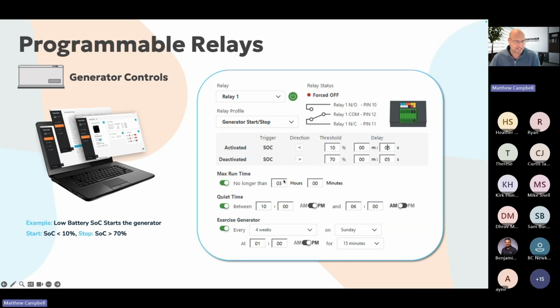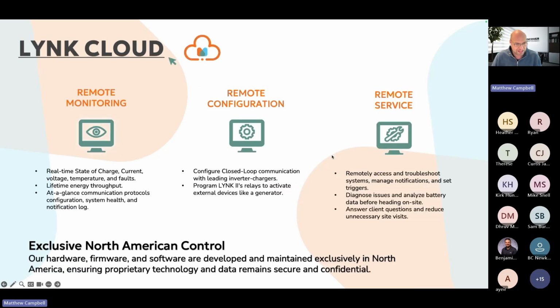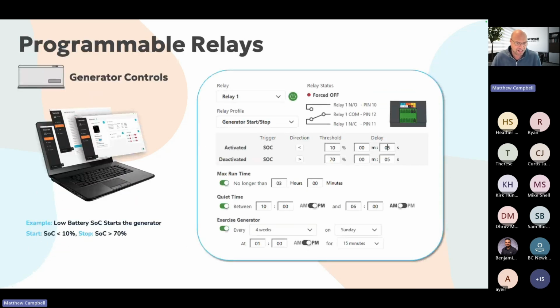Where I find this maximum runtime becomes a really powerful tool, utilizing the Lynk as opposed to using an inverter AGS, is, as a for instance, you've got your PV array set up, and you're consistently running down to an SOC of 10% at say 5 in the morning. Sorry, I'm bouncing on slides here. Sun comes up at 8 in the morning. You of course don't want to run your generator to 70%, because then you're not utilizing your PV. So you want it to run for 3 hours. Sun comes up at 8 o'clock in the morning, the generator shuts off and your PV array takes over.